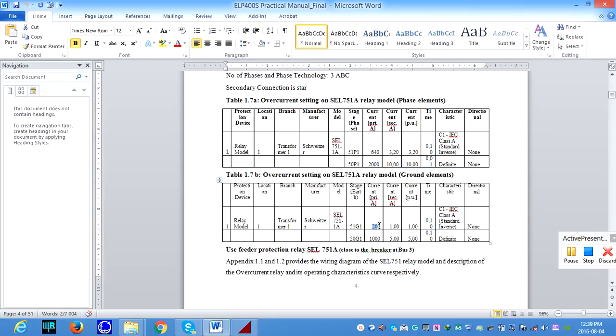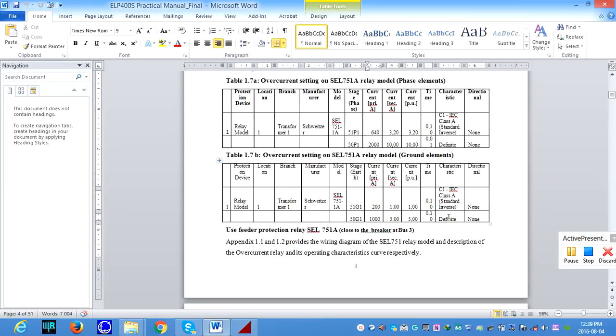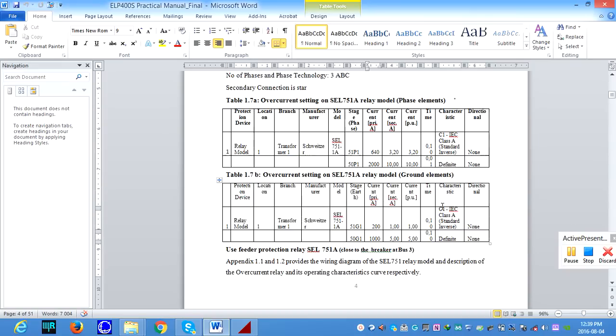For the ground elements, keep it in mind, anything from 200 to 1000 amperes is going to be inverse characteristics, and from 1000 onwards is going to be a definite characteristic. It means from 0 to 200 amperes the relay will not trip. If the current reaches 200 amperes up to 1000 amperes, the tripping will be done due to the IEC characteristics, and from 1000 amperes onwards it's going to be the definite characteristic for the ground elements.